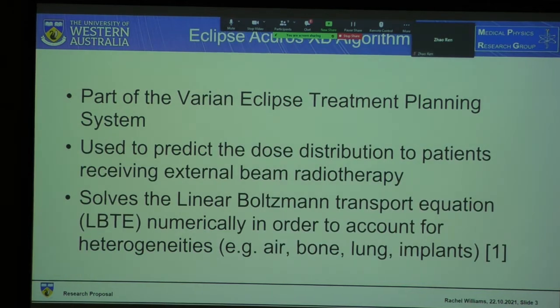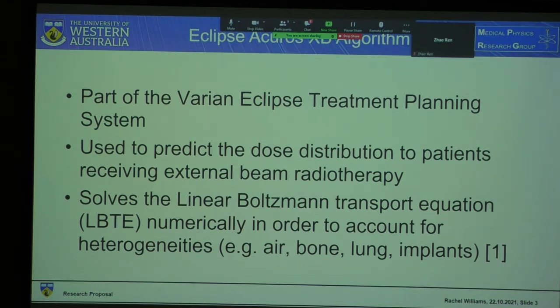The Eclipse Acuros XB algorithm is part of the Varian Eclipse treatment planning system. It's used to predict dose distributions to patients receiving external beam photon radiotherapy, which it does by solving the linear Boltzmann transport equation numerically in order to account for various heterogeneities including air, bone, lung, and implants.